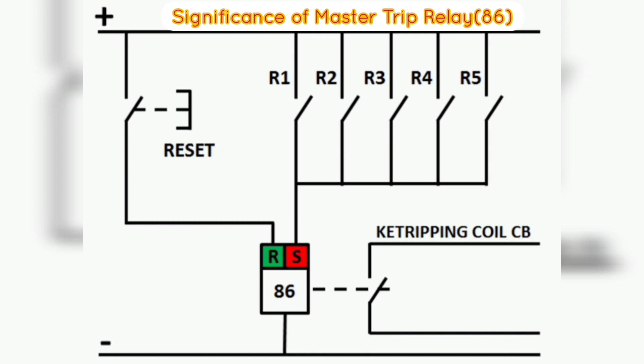If we use a Master Trip Relay, we need to carry only two wires to the tripping coil. Third, the Master Trip Relay has multiple contacts that can be used for interlocking, for tripping other breakers, annunciation, and signaling to PLC or SCADA.